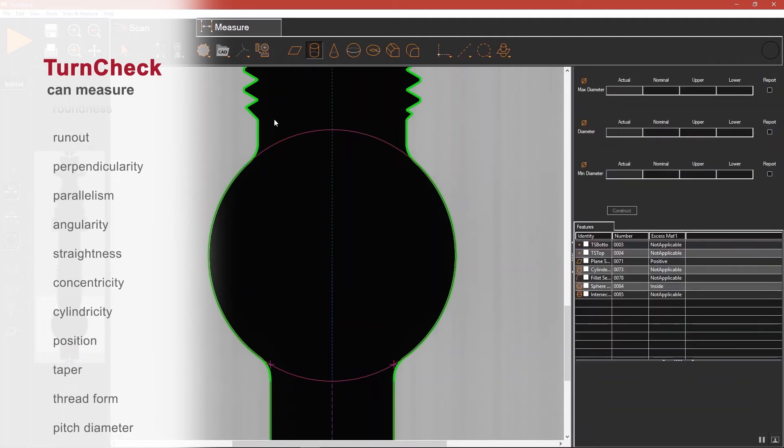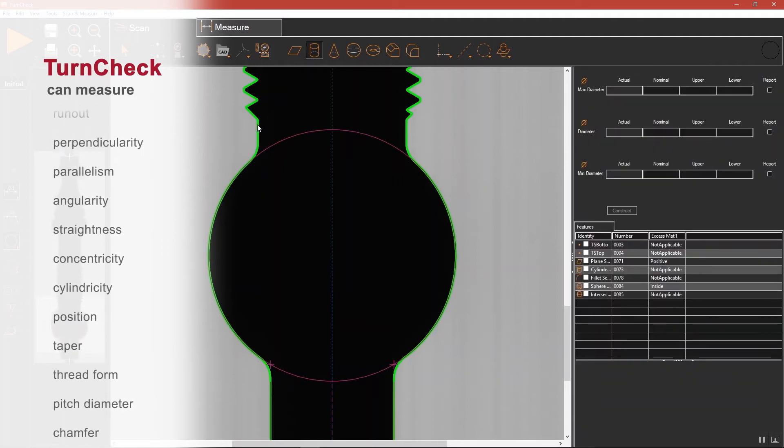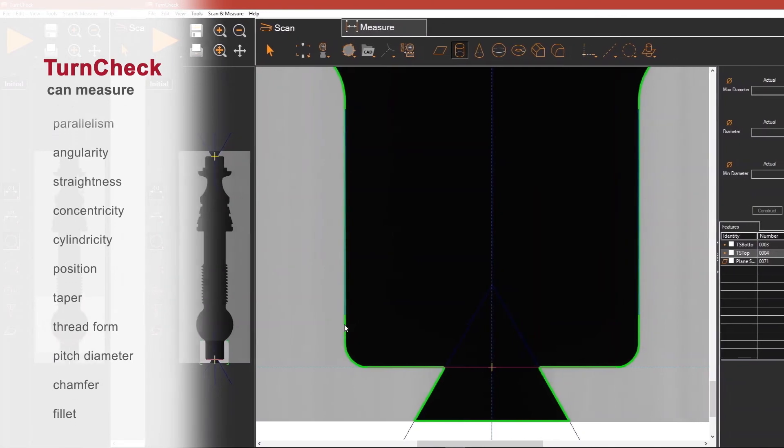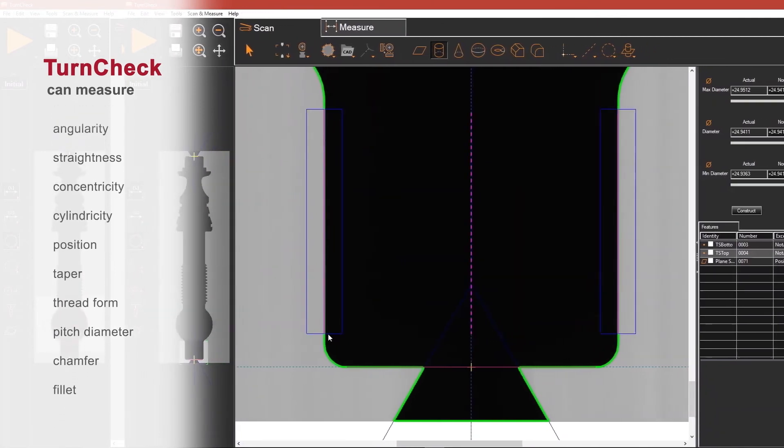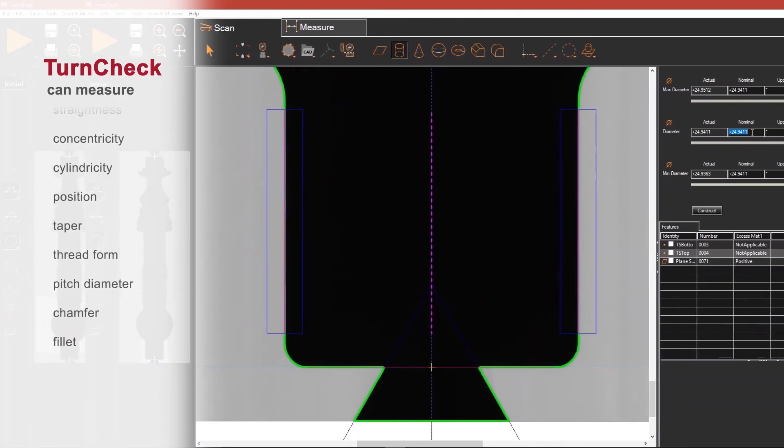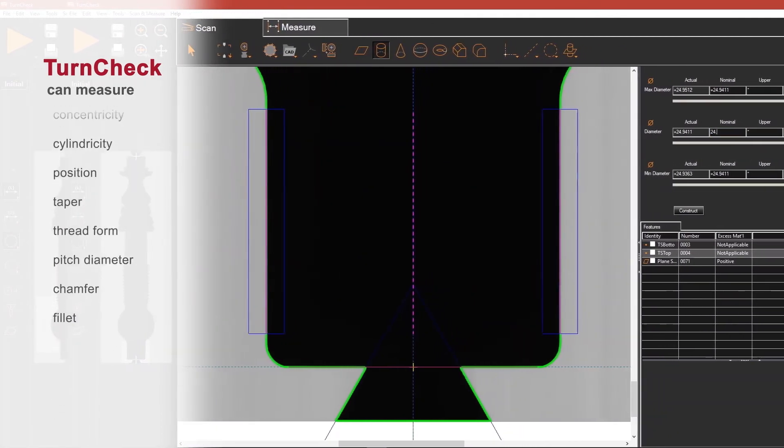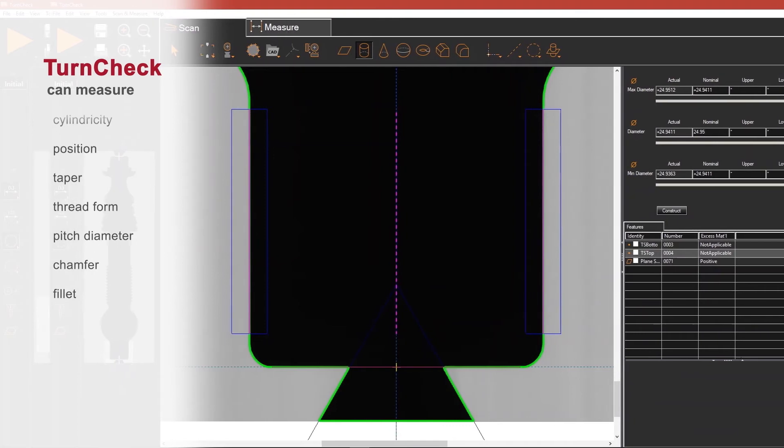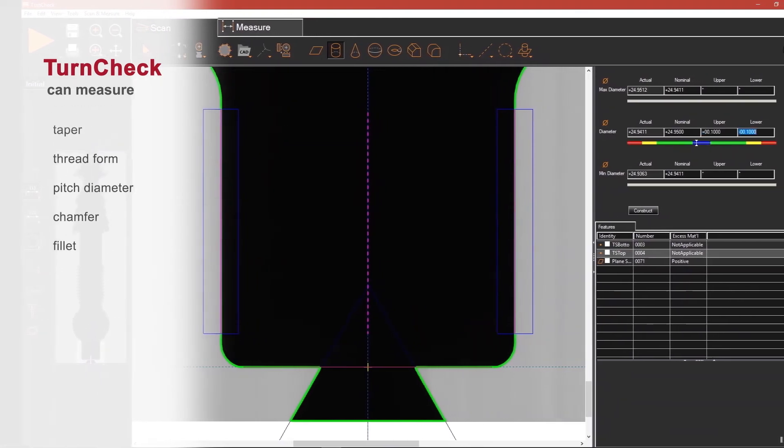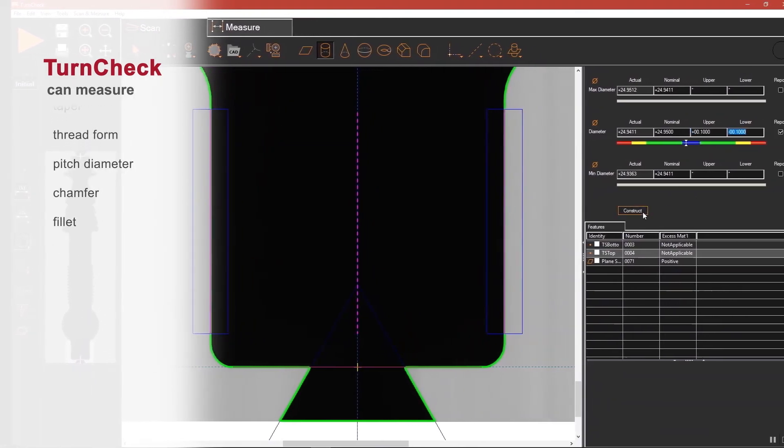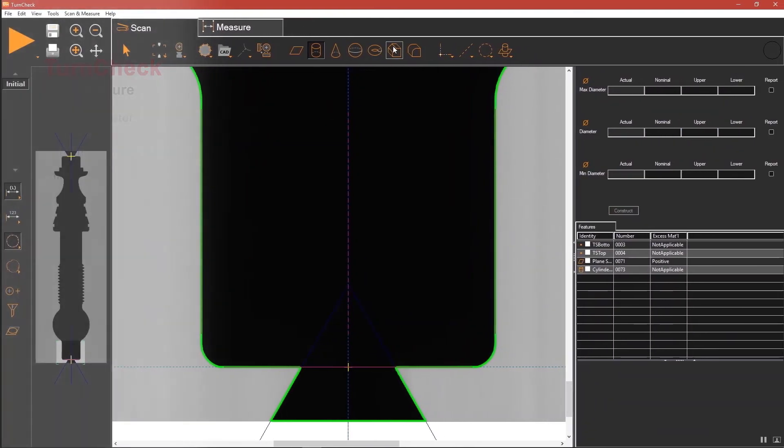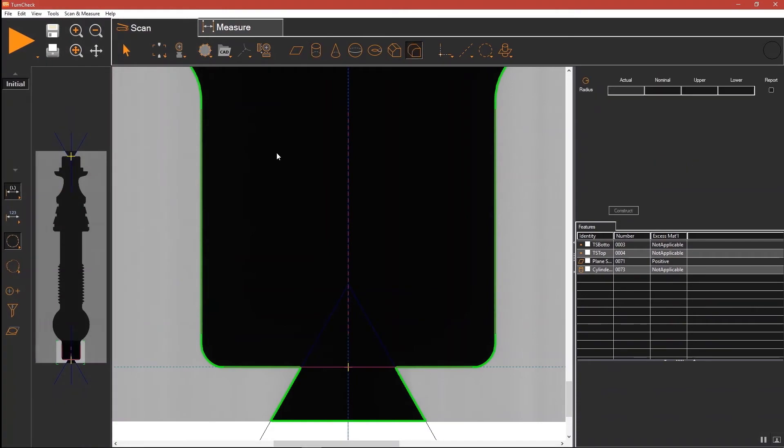Pre-programmed parts report dimensions and apply tolerances automatically. To set up a new part, the operator selects the features of interest on the screen, inputs nominals and tolerances, and saves the routine. Setup time is just a few minutes.